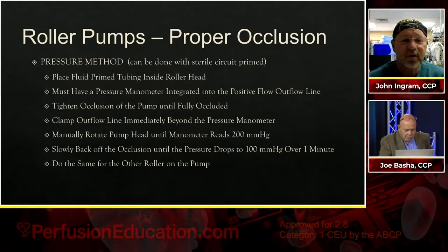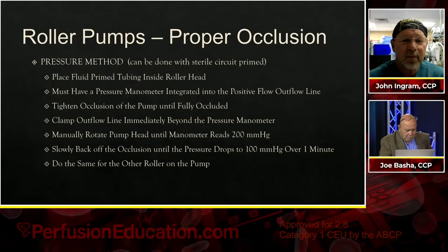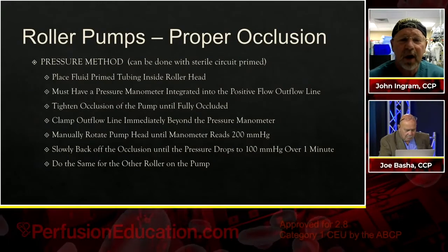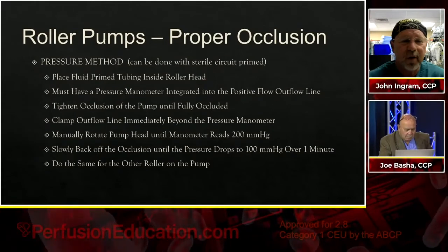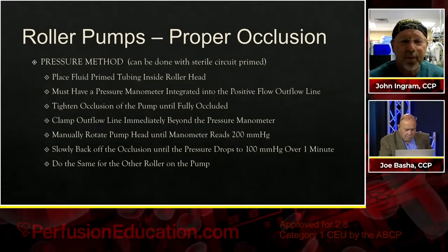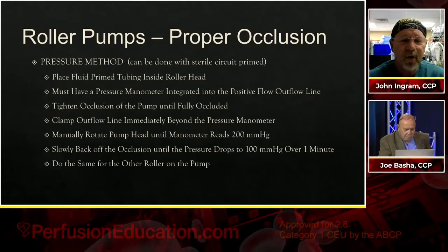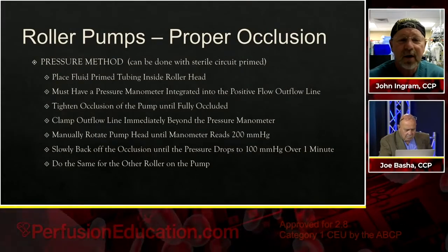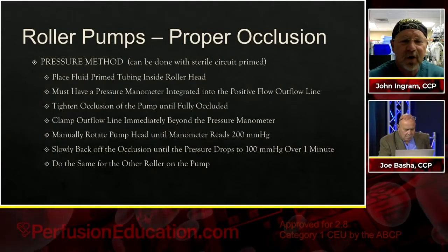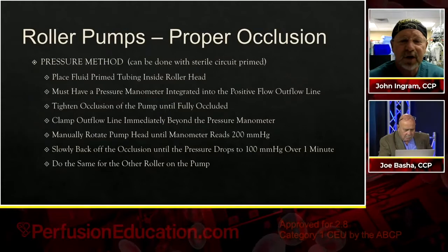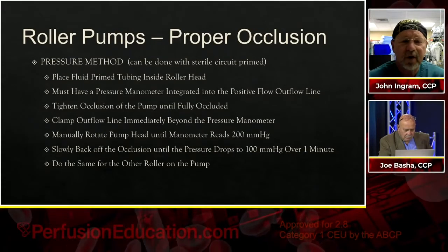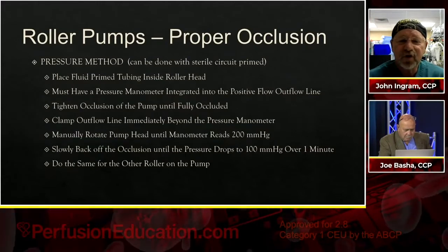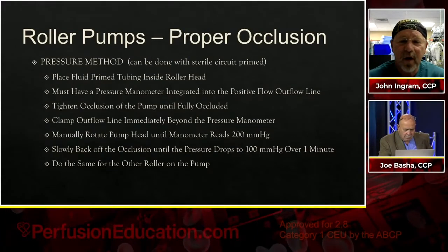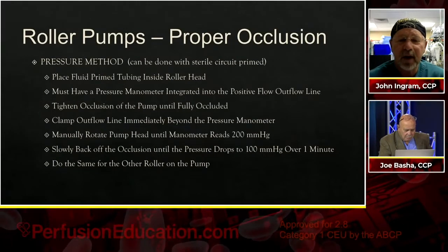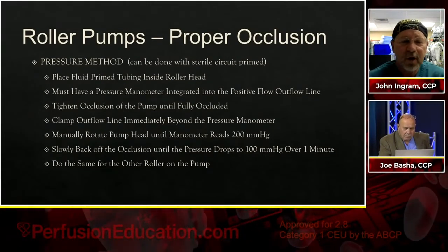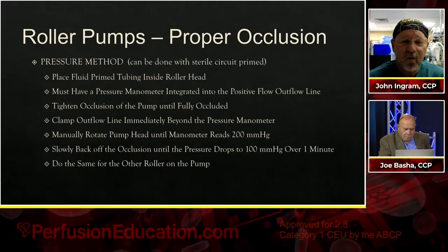You've primed your circuit and there's fluid in the tubing and inside your roller head. You then must have some type of pressure manometer integrated into the positive flow outflow line somewhere. You then tighten the occlusion of the pump pretty much until it's fully occluded, and then you clamp your outflow line somewhere just beyond the pressure manometer. Then you manually rotate your pump head until the manometer goes up and reads 200 millimeters of mercury. Slowly back off of the occlusion until the pressure drops slowly over a 1 minute period down to 100 millimeters of mercury. So it should take about a minute for it to drop from 200 to 100. And then you have to do the same for the other roller on that same pump.